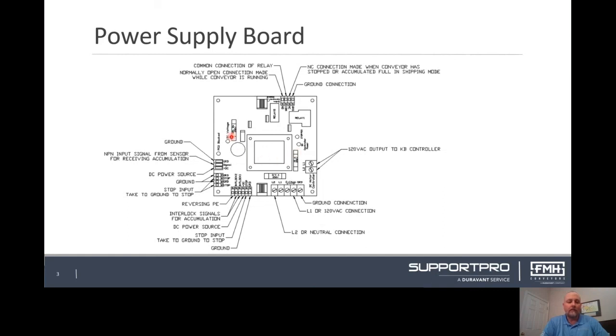The 2 amp fuse controls the DC voltage output to the power supply. This is used to control items such as accumulation photo-eyes and your stop circuit. If this fuse is blown, there could be a short in the communication cable or a short in the photo-eye cable. Check for any wear or damage to these wires.